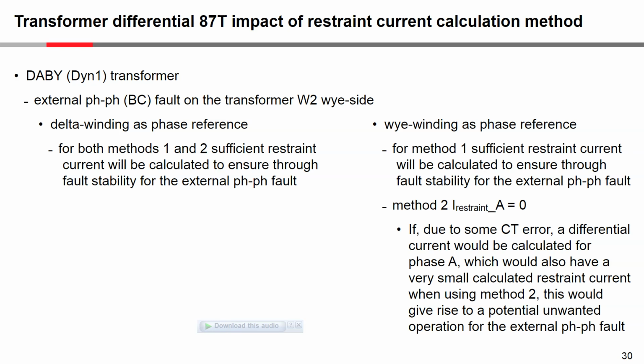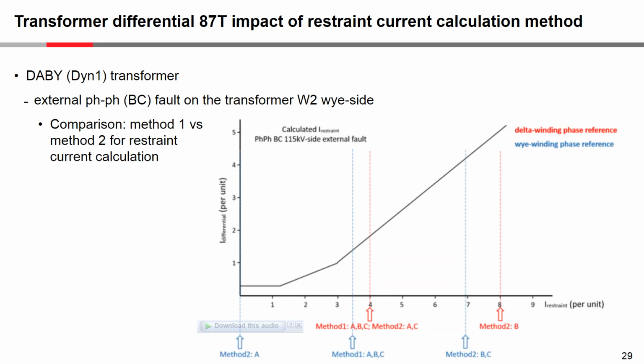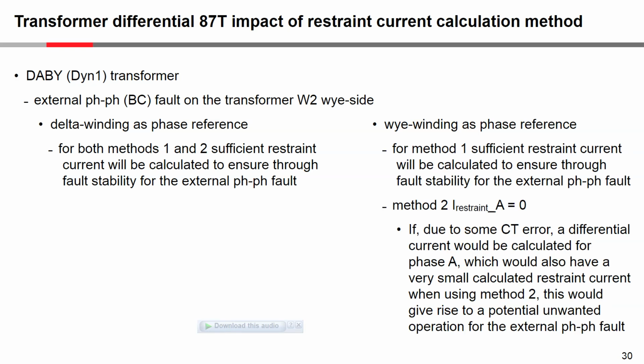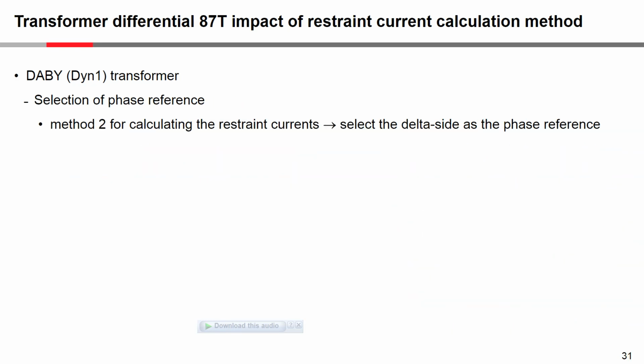So we've calculated very, very small restraint, and even if it was some small value, not exactly 0, we're in the most sensitive part of the characteristic. So a small amount of differential current could then potentially go into the operate area, and we could get a misoperation. And such a small amount of differential current could be due, for instance, to some small CT error or something like that. So what can we say then for selection of phase reference?